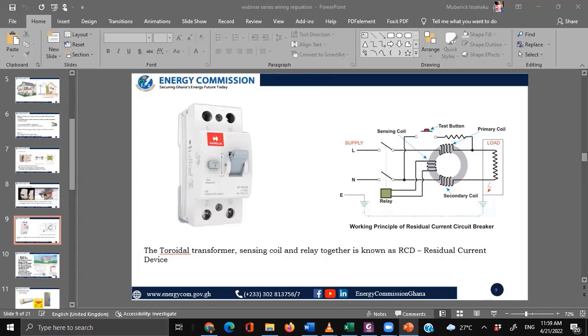So we know now that the RCD doesn't trip on short circuits, it's the MCB that does. So people will be asking again, then why don't we just buy MCBs? Does the MCB do the same function as the RCD? That is not true. The MCB will trip on overload or overcurrent. Then the MCB also trips on short circuit. The RCD here is comparing the neutral and the live current. It sees some deficiency in them, then it trips. So the RCD is tripping on residual currents.